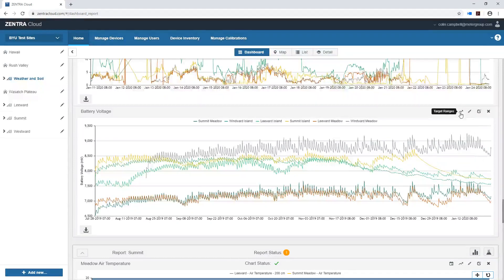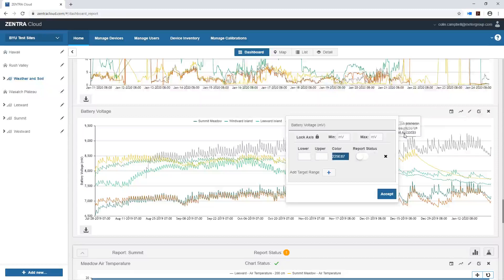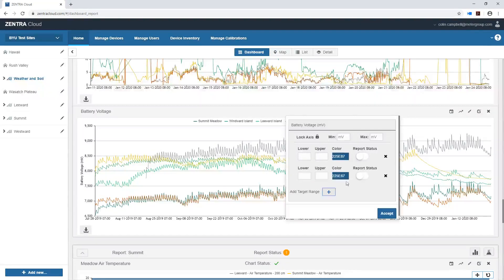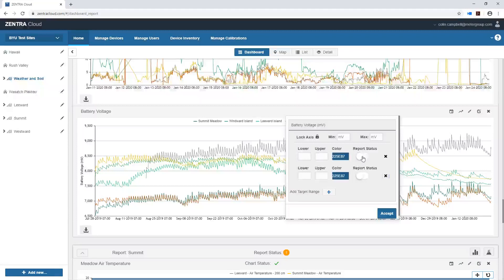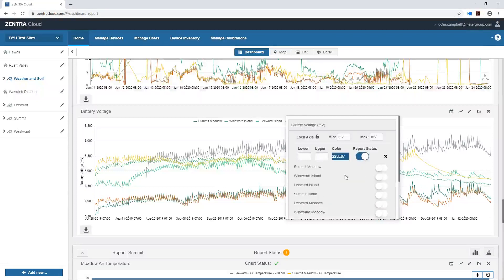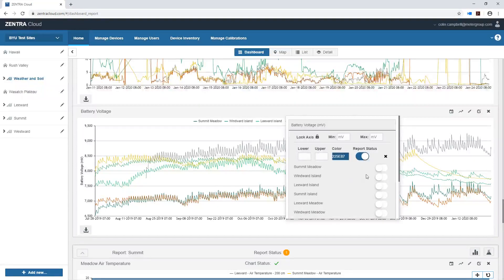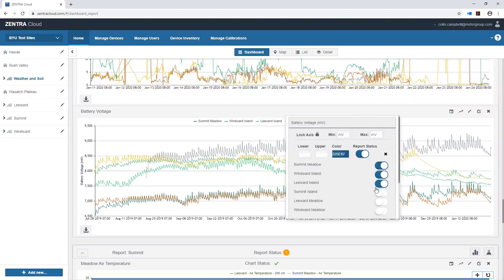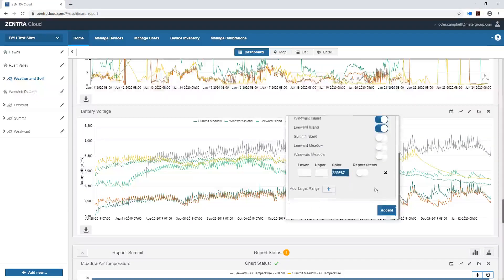I also have the option here to set up target ranges on this graph to alert me if I set up this range to alert me whether the battery voltage is below an acceptable level. So I can turn some of these on and then it will send me an email if there's a problem.